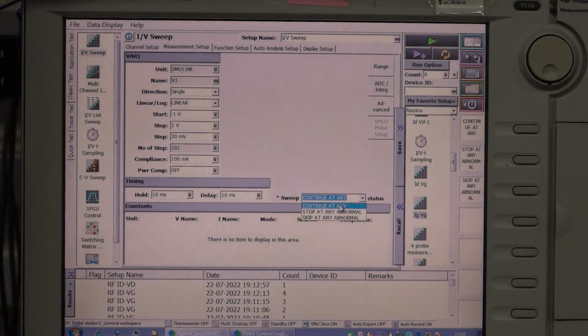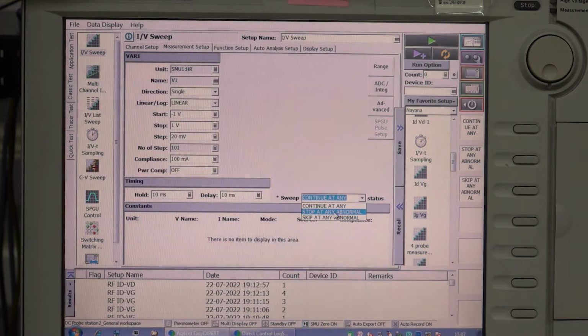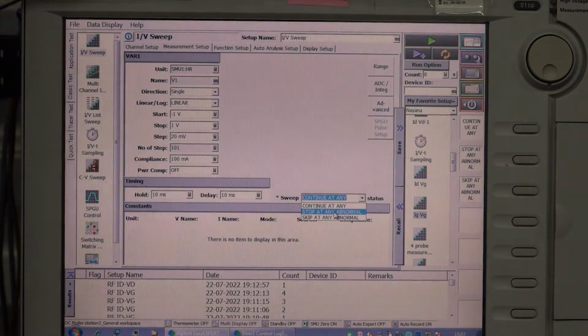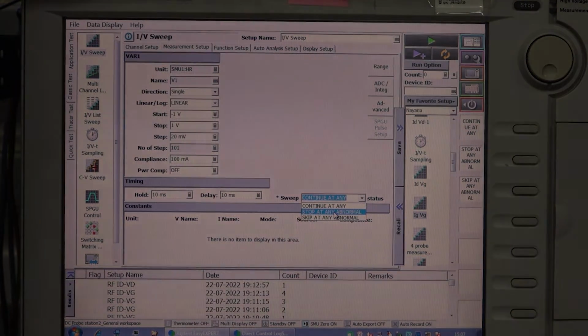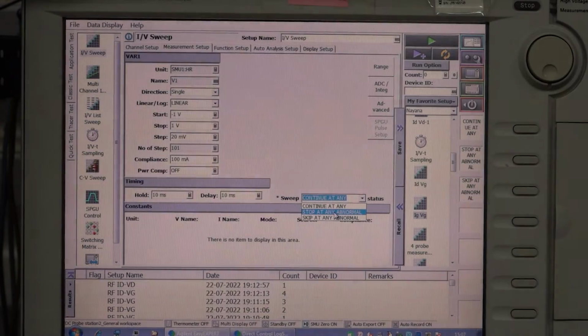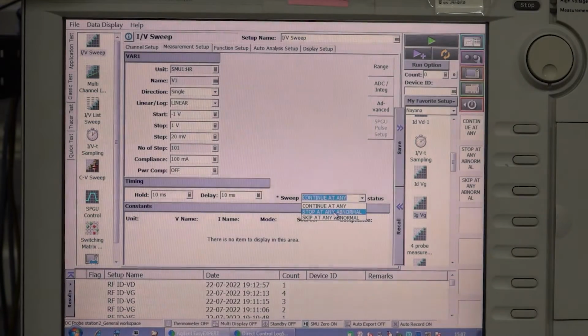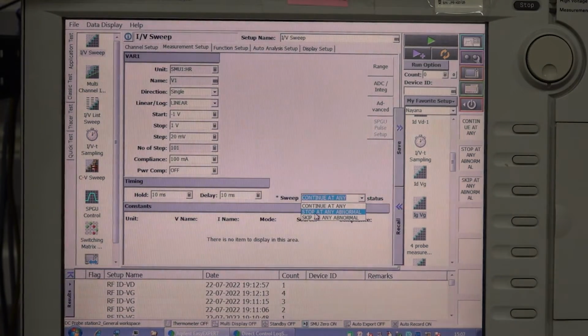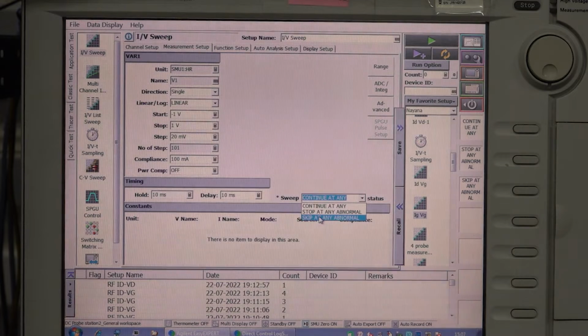So continue at any means normally it will carry the measurement without any hold or error. Stop at abnormal means if there is any abnormal condition, say like the device is shorted. Normally if you measure some pico range of current and all of a sudden the device is shorted, because of which we get 100 milliamps of current, the instrument will detect that abnormality and stop the measurement. Skip at abnormal means if any abnormality exists, it will still skip that abnormality and start measuring. So normally we use continue at any.